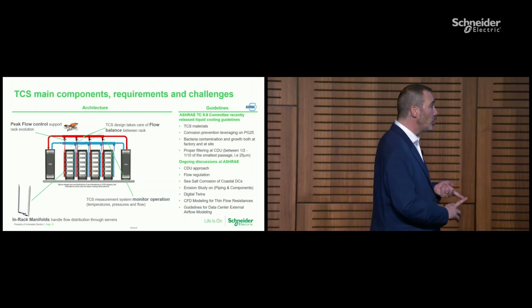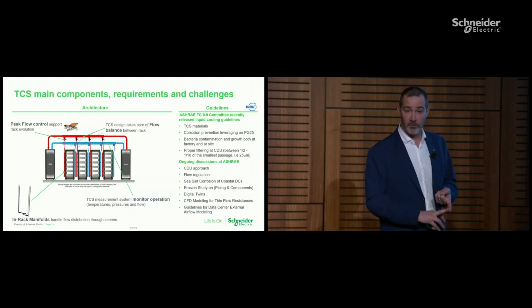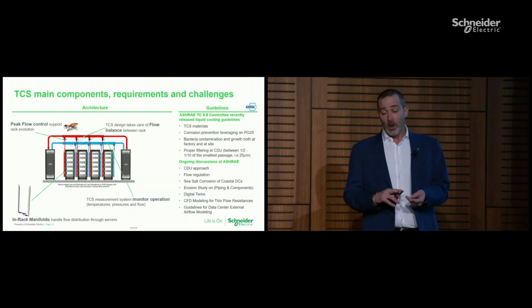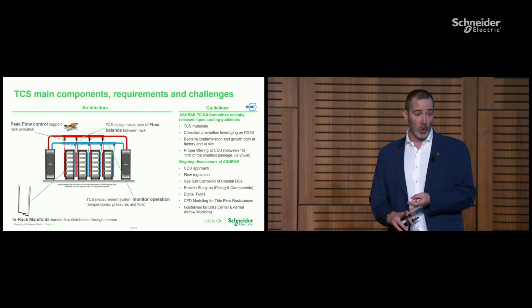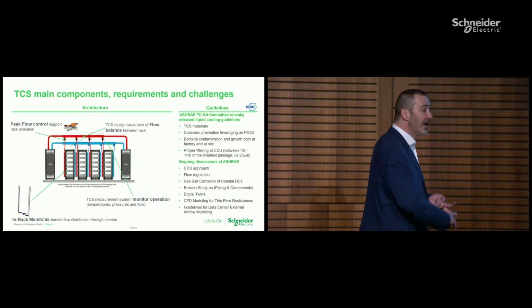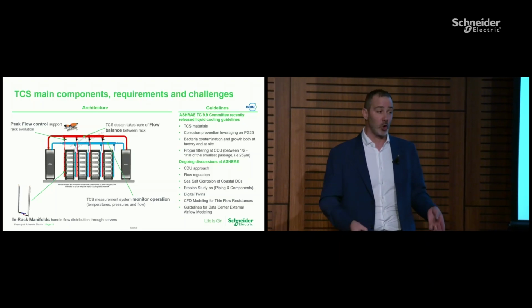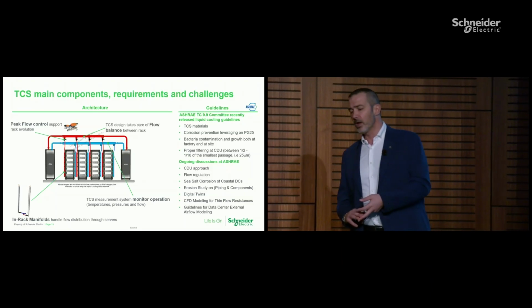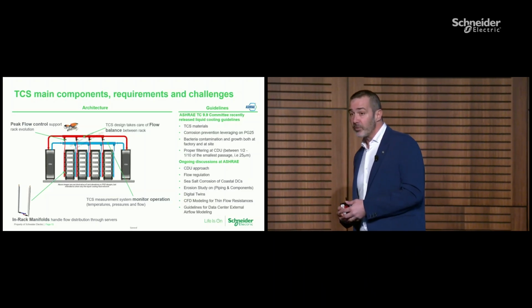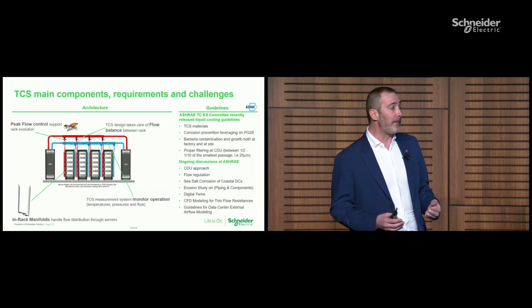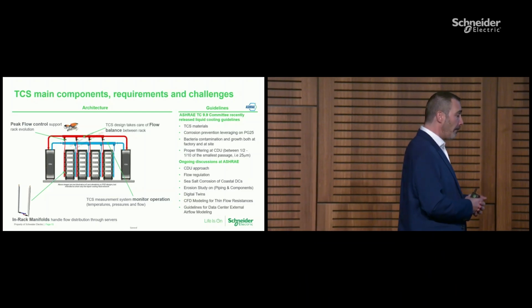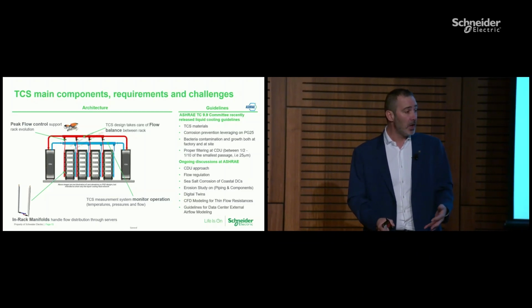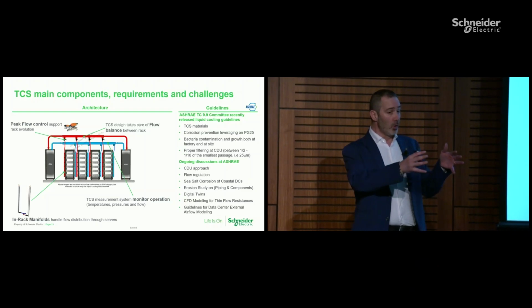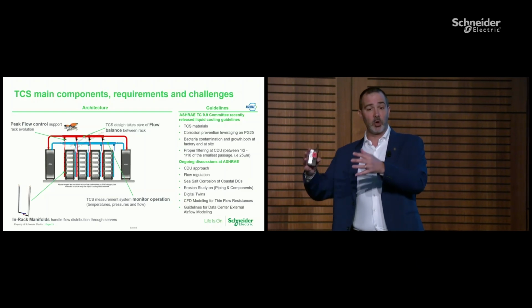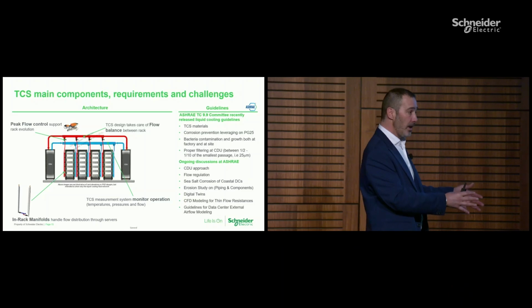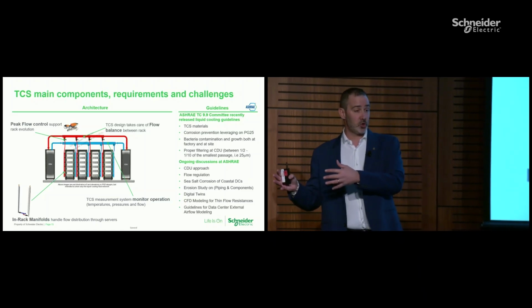They are defining how to do the TCS, which material to use, for example stainless steel, which kind of fluid, again PG25, regardless of whether you are in a very warm climatic condition you must use glycol inside. However, you also need to check how to prevent biological contamination, because this can happen at the factory, during transportation, and during installation, and may impact severely on the server.